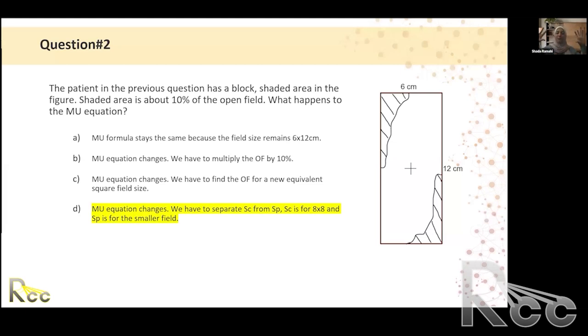So we have now two types of scatter. We have collimator scatter, the scatter coming from the machine, and that is identified by your field size, 6 by 12. So the collimators have opened to 6 by 12, and you have this scatter coming from the machine. And then we have a smaller field size, right? We have introduced a little bit of shielding. So what's going inside the patient is a smaller field size, identified by whatever scatter remains after we remove the blocks, and that is what we call the phantom scatter. So in fact, we will have two different field sizes: the collimator scatter field size, and then a smaller field size that goes with the phantom scatter.